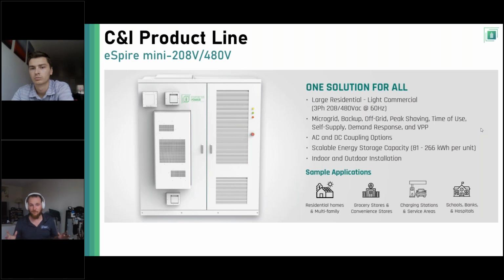This system can be installed indoors or outdoors. Indoor installation can be tough because you have a lot of code requirements. It passes all the 9540A and UL 9540 tests for thermal runaway and compatibility with the inverter. However, you are still beholden to the inspectors and local jurisdictions. So if you can fit it inside per the code, great, it can go inside, no problem. But it's also NEMA 3R, so it's fully equipped to go outside as well.